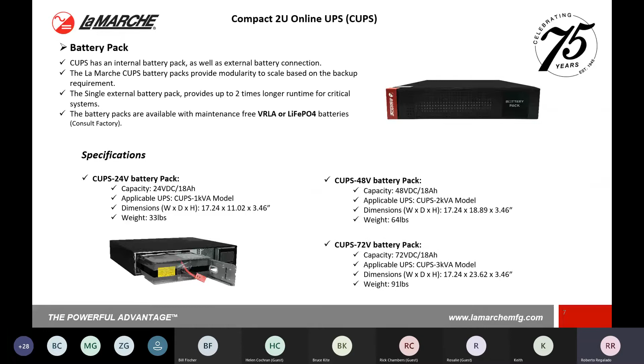The battery packs we have available right now are the 24 volt, 18 amp hour for the 1 kVA, 48 volts 18 amp hours for the 2 kVA, and 18 amp hours for the 72 volt power module.